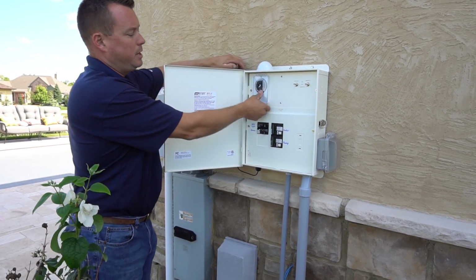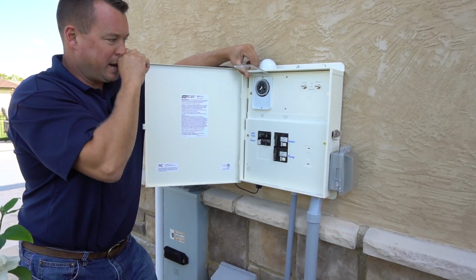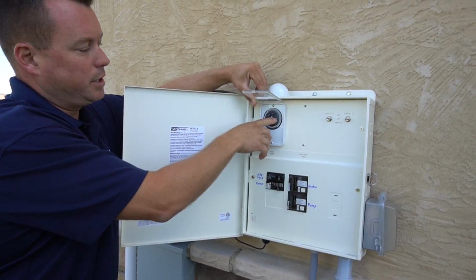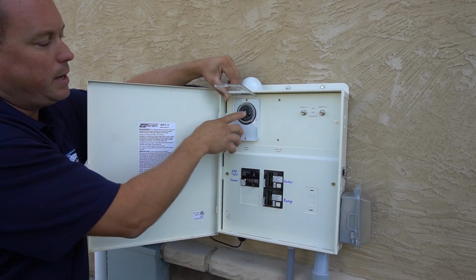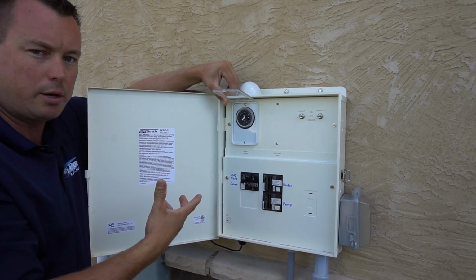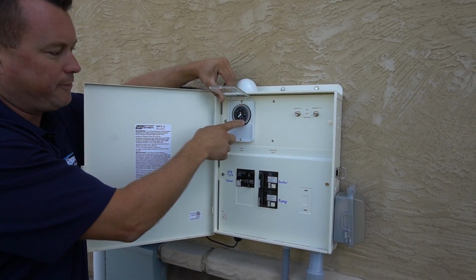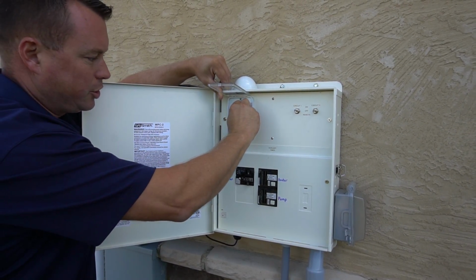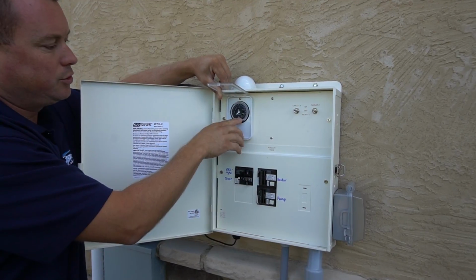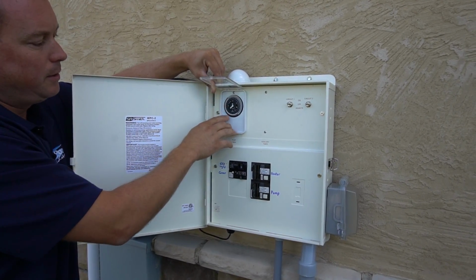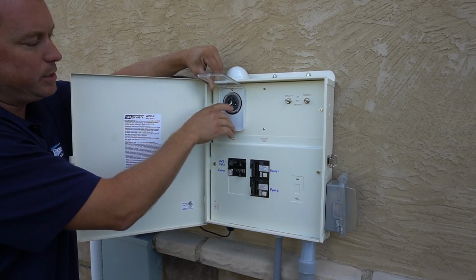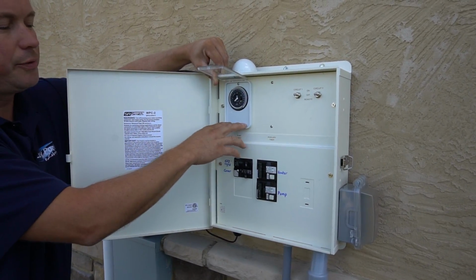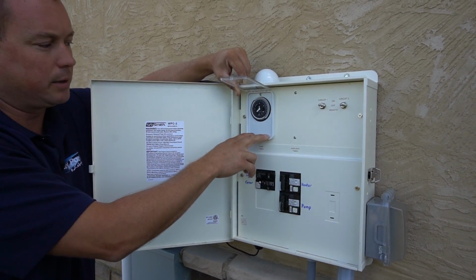Let's start with the timer. The timer has three positions here on it, on this little switch. The up position is pump on, no matter what the timer is set for. The middle position is to run based on the timer. And then the bottom position has a zero, which means off, regardless of the timer settings.